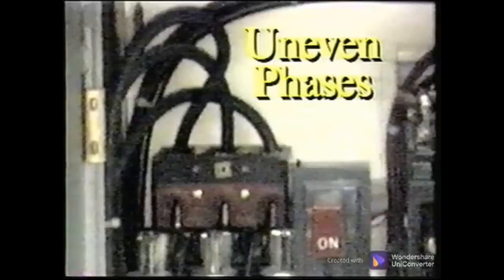When scanning a panel or junction box, the temperatures may all be within tolerances. There are no loose connections, bad fuses, or breakers, and yet there is still an obvious anomaly. This problem is that of uneven phases. Since most industrial facilities use three-phase power, there will be three phases or legs going to machinery and equipment.